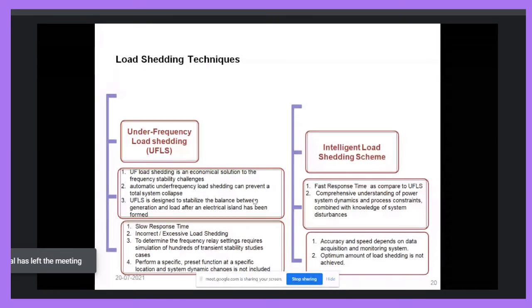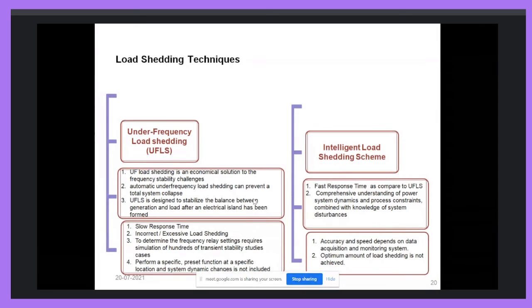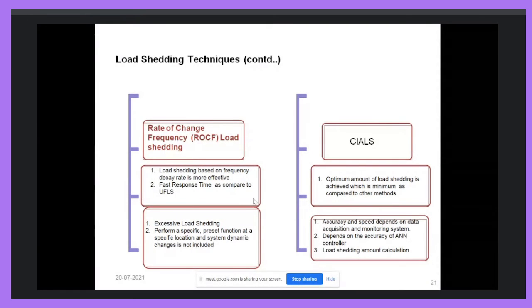But in an intelligent load shedding scheme, we have to establish a monitoring system and a data collection system, then we have to process that data, and we have to use a fast machine in which the artificial neural network is installed. Then we have to install a fast processing system. So these are costly systems as compared to the under frequency relay based load shedding, but the system is much more accurate and adaptive. There is no great loss of the load. Also, there is some other classification.